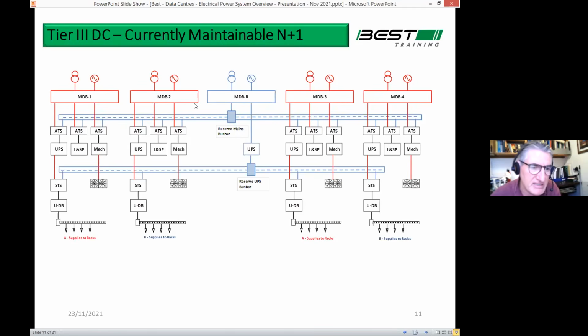And it means if you want to come in and plan, say, I want to take this main board out of service and work on it, well, I don't want the servers fed off that board to go down. So what you do is you transfer the power over onto the reserve line. And then you work on MDB1, you service it. Then you work on MDB2 a month later and you service it, and MDB3 and 4, etc. And of course, it also works in the event of a fault. If the system power failed, the first thing it would do is try and start its generator. If the generator didn't work, well, then it would transfer onto the reserve line.